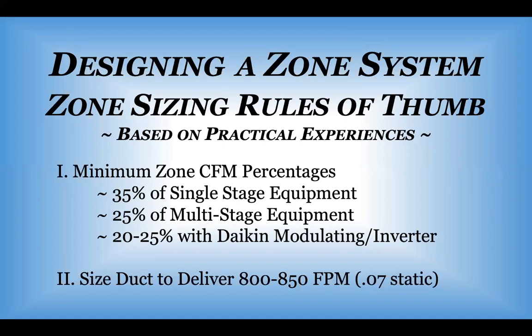Going back to duct sizing, deliver 800 to 850 feet per minute. Design that duct at 0.06, 0.07 in that range. Do not design your duct system with 1,000 feet per minute with a 0.1 static.